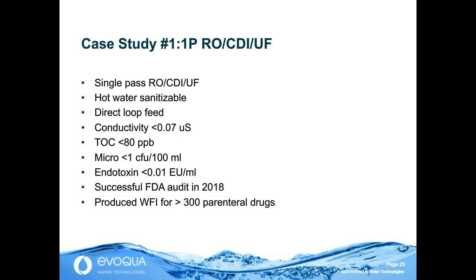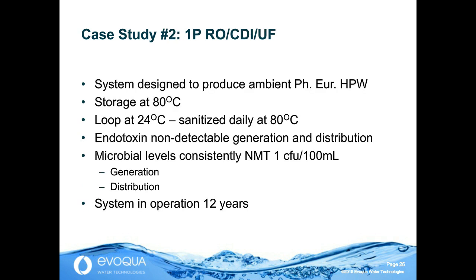Another case study, single-pass RO, CDI, ultrafiltration. This was designed to produce European Pharmacopoeia highly purified water. The water is stored at 80 C. The loop is maintained at 24 C and hot sanitized daily. Endotoxin is consistently non-detectable in generation and storage. The micro is basically at the limit of detection consistently, and this system has been in operation for 12 years, so proven over a lengthy period.